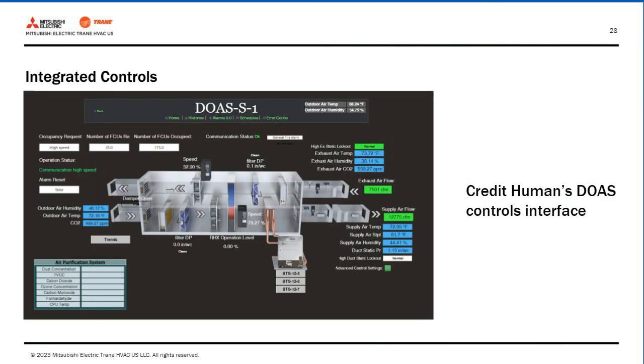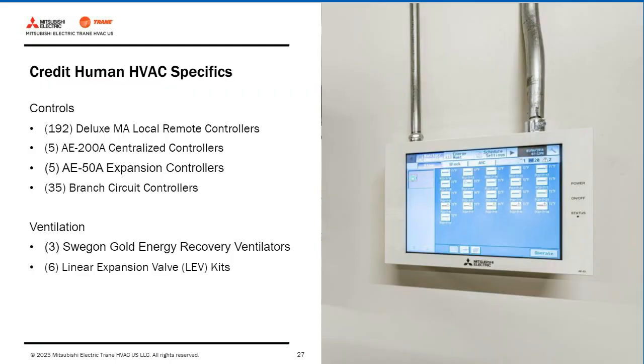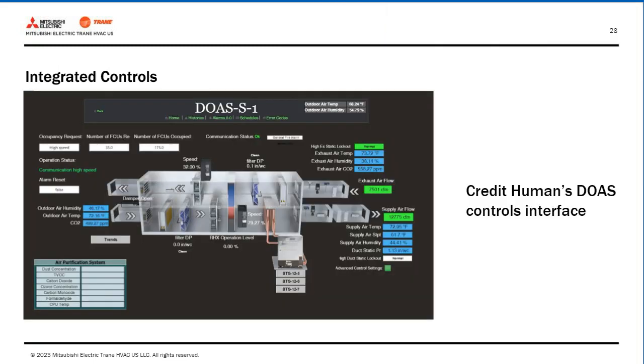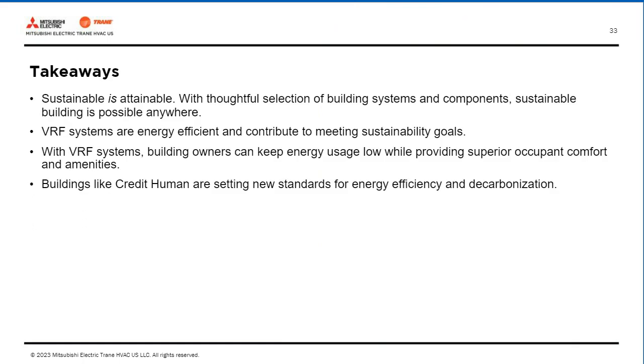So actually, this screen that you're looking at here is from the BMS system, or what we call the DDC system. The whole VRF system is tied into Trane. Actually, Trane has the control system set up on this building for the BMS. So everything is in that BMS system: the lighting controls, all of our VRF systems, the DOAS unit which you're showing here, the whole condenser water loop system and the geothermal loop system. We can see all of those pumps and units and everything. This little controller on here is dedicated just for the VRF system. That controller is integrated into the BMS system so that we can see all of the units on this specific controller. So yes, it can be, and it is, on this Credit Human building.